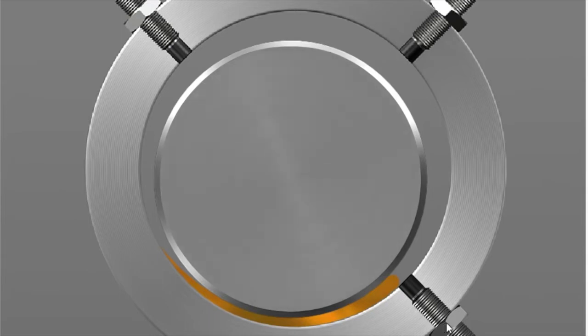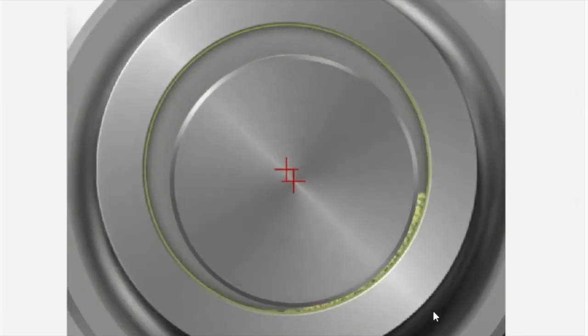The third probe here is not in the same plane as these ones. This one might be at the end of the rotor or somewhere where there's a key or keyway, and it measures that displacement, and that gives us our once per revolution information.